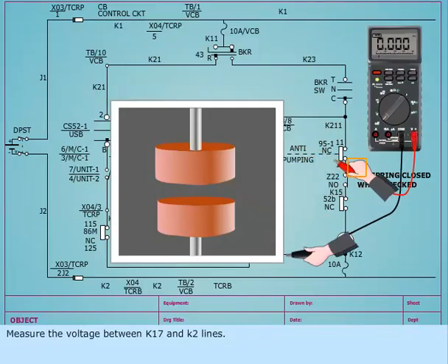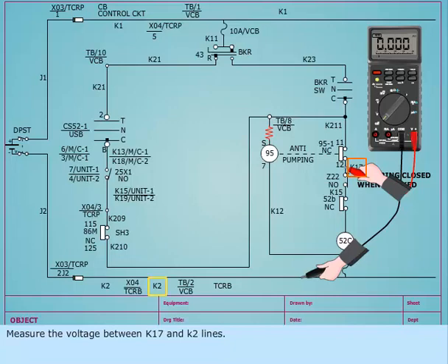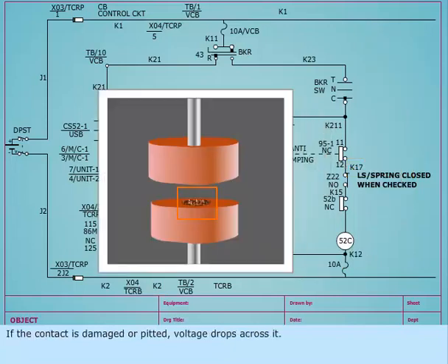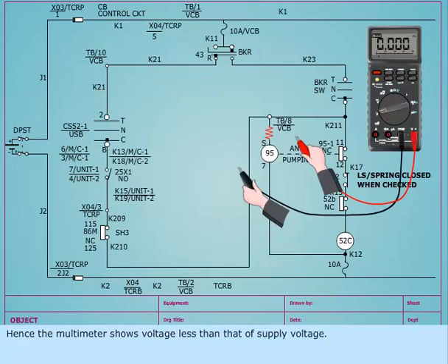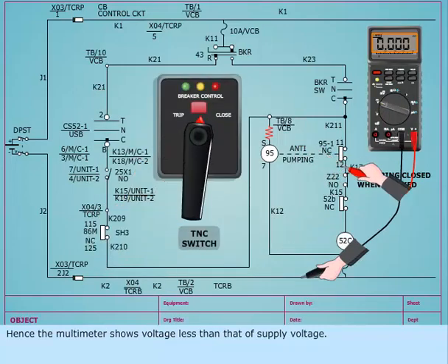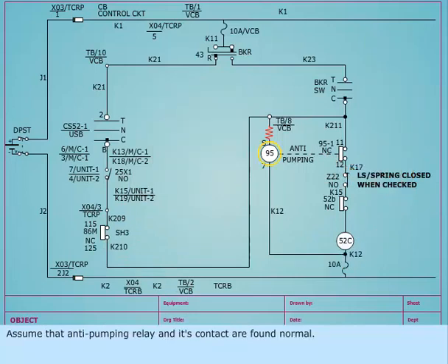Measure the voltage between K17 and K2 lines. If the contact is damaged or pitted, voltage drops across it. Hence the multimeter shows voltage less than that of supply voltage. Assume that the anti-pumping relay and its contact are found normal.